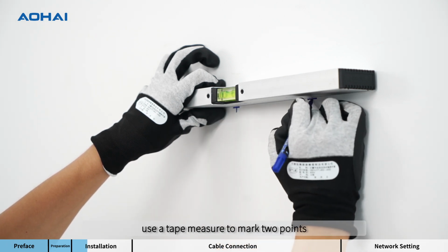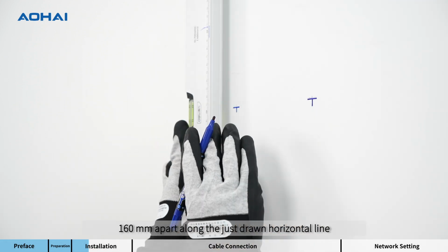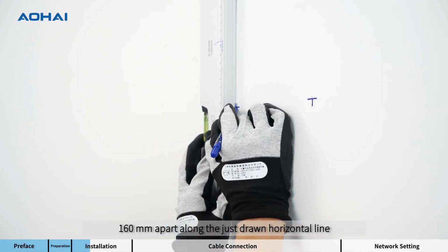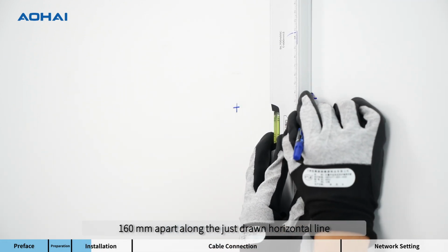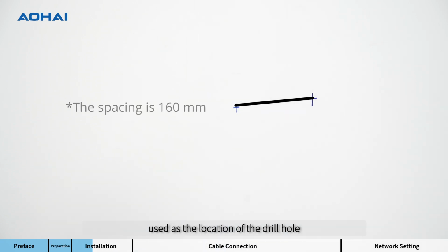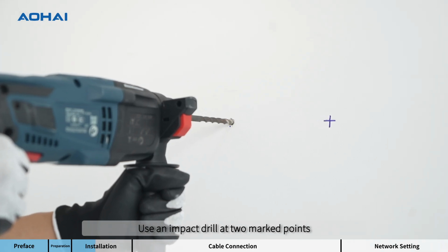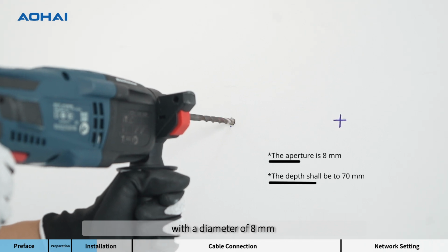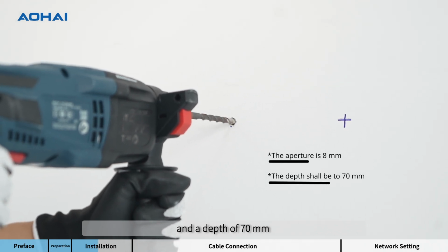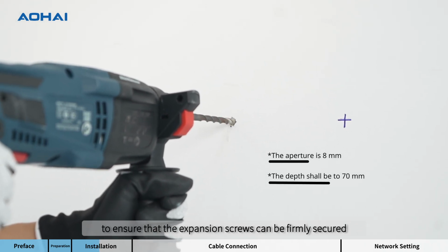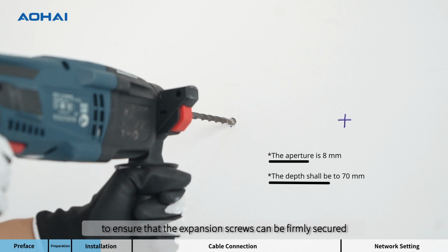Next, use a tape measure to mark 2 points 160 mm apart along the just drawn horizontal line. These 2 points will be used as the location of the drill hole. Use an impact drill at 2 marked points with a diameter of 8 mm and a depth of 70 mm to ensure that the expansion screws can be firmly secured.